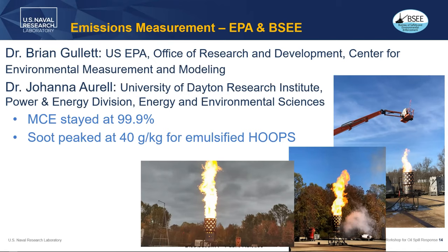We'd measured soot before and had pretty low soot emissions, but the modified combustion efficiency we hadn't measured before at all. We were really pleased with the results. The high-speed turbulent mixing really ensures that the oil mixes out and burns well.